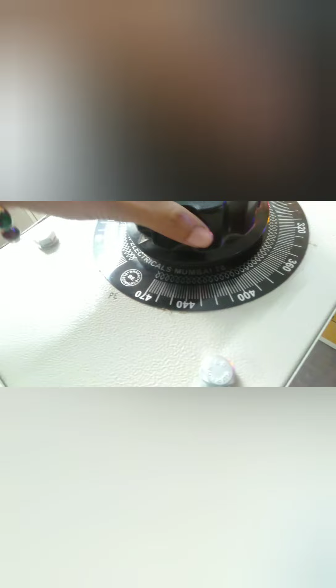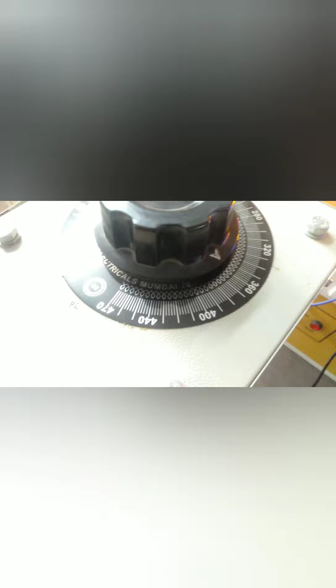now make it 0, because we are going to change from no load to block rotor. So for getting the block rotor test reading, we have to make the dimmerstat 0. Now if you see, this is at 0. When we are giving 0 voltage, all the readings will come out to be 0. Then switch off the supply and do the connection for the block rotor test. The connection is the same, there are no changes in the connection.